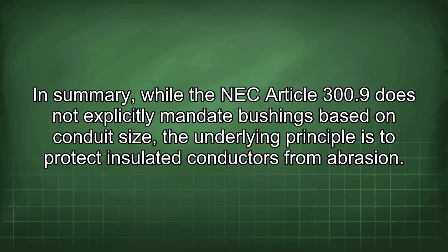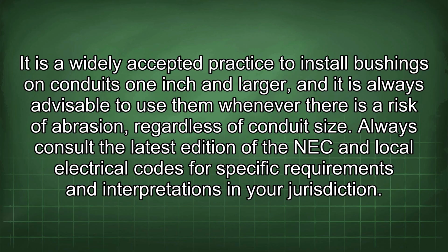In summary, while the NEC Article 300.9 does not explicitly mandate bushings based on conduit size, the underlying principle is to protect insulated conductors from abrasion. It is a widely accepted practice to install bushings on conduits 1 inch and larger, and it is always advisable to use them whenever there is a risk of abrasion, regardless of conduit size.